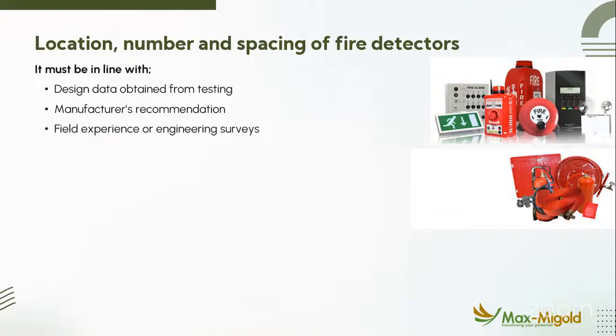All right. So if I'm in an IT data center room, a comms room, and it has a raised floor, the volume of that space is not from the raised floor; it's from the original floor. I'm going to measure the height of the building so that we can design the appropriate FM 200 that will be there. But for smoke detectors, it's just the length times breadth. All right. So it helps us to know the location, the area, and the obstructions in place, as well as the hazards that you have in that space, what you are keeping, the activities you are doing in that space. That will help us to know how many smoke detectors we should have.